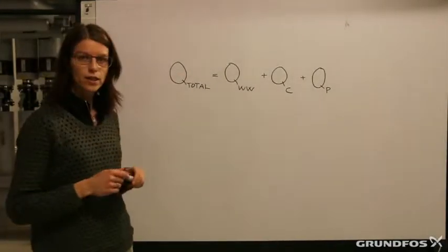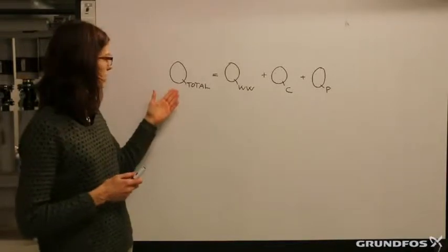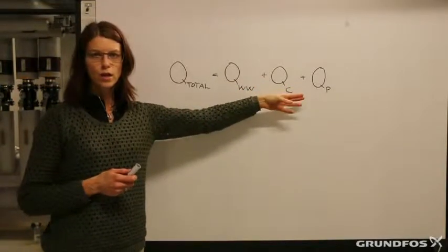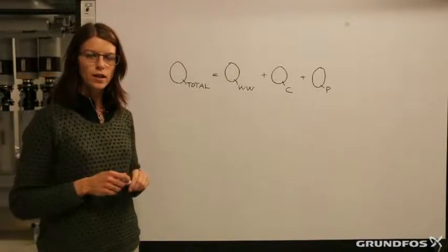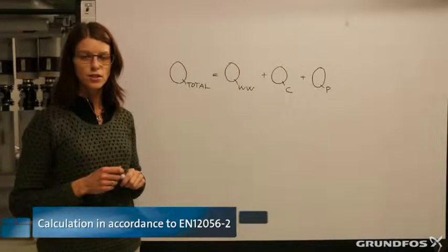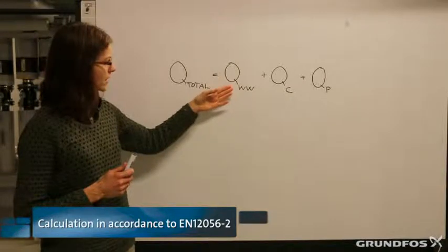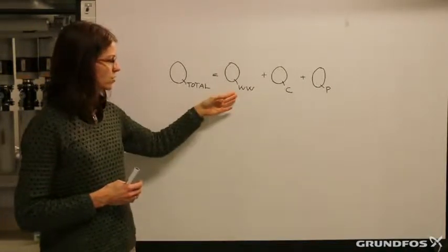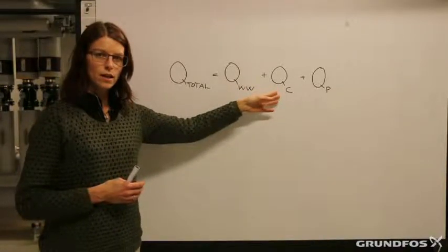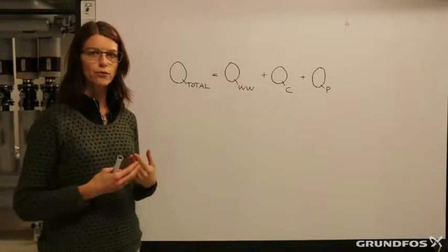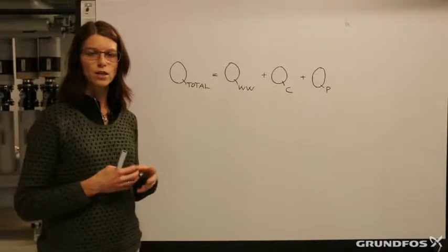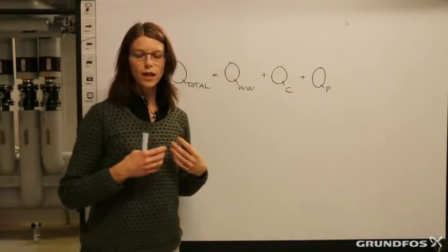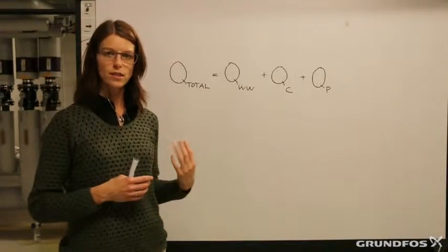The formula for the calculation of the total wastewater flow rate is shown here. Q_total equals Q_wastewater plus Q_continuous plus Q_pumping. This formula is from EN standard 12056-2. The Q_wastewater is the discharge from the different discharge units. The Q_C is the continuous flow rate — it could be for example from a grease separator with a nominal size of seven liters per second. And Q_P could be a pumping station adding flow to this wastewater system.